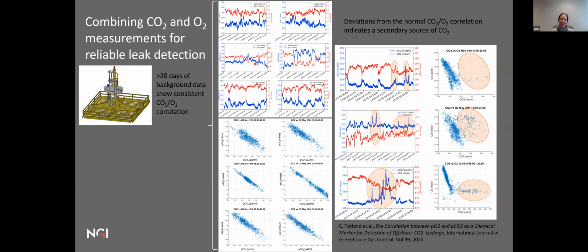And one of the interesting findings that we had was the extremely high degree of correlation between oxygen and CO2 when you don't have a leak. If you see, the CO2 is the blue line here. Each plot shows a 12-hour interval of data, and the red line is oxygen. And as you can see, these mirror each other very, very well. And this is because these 2 parameters co-vary naturally. And if you plot them, you can also see that they have a very nice linear relationship.